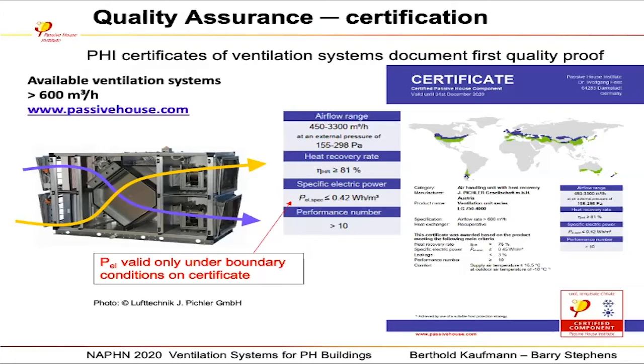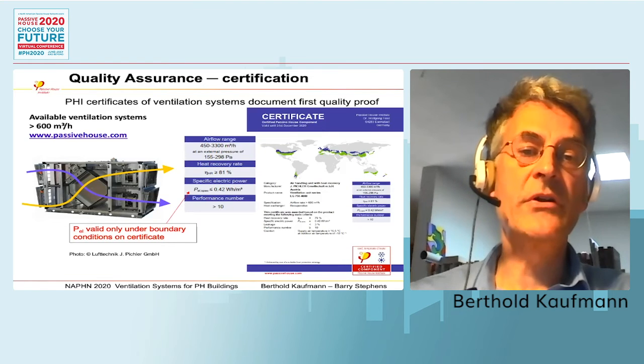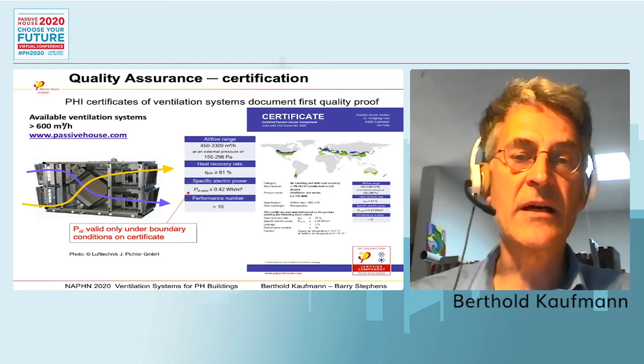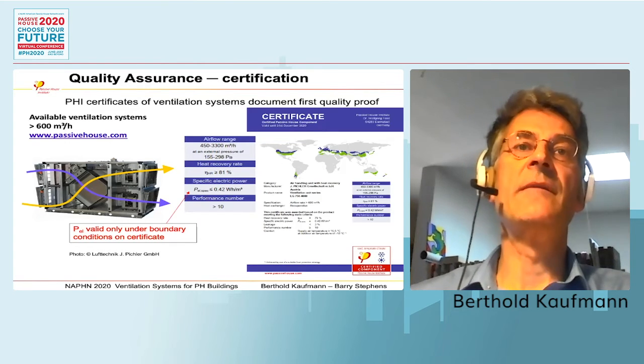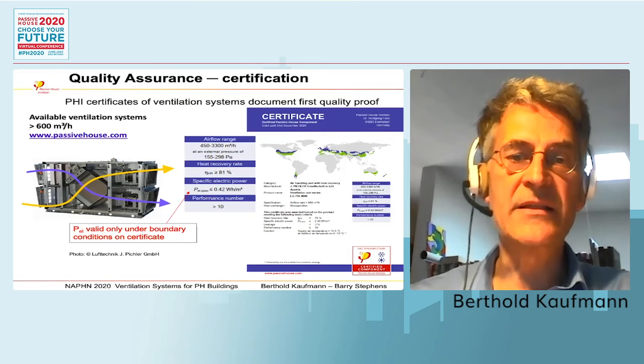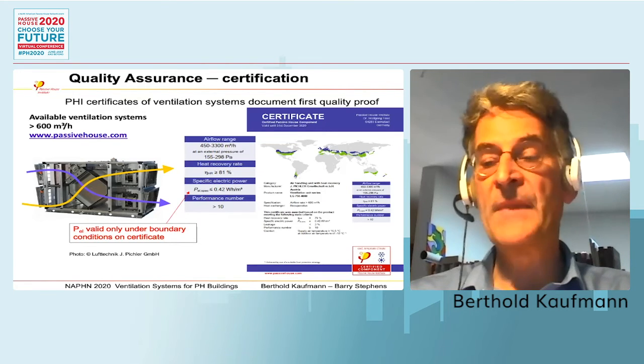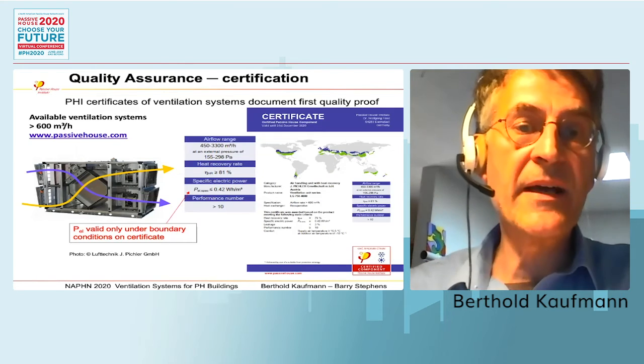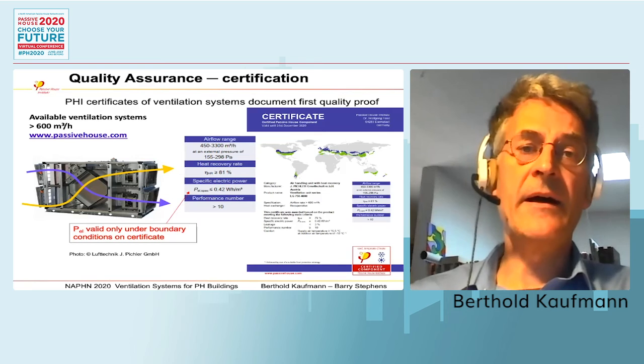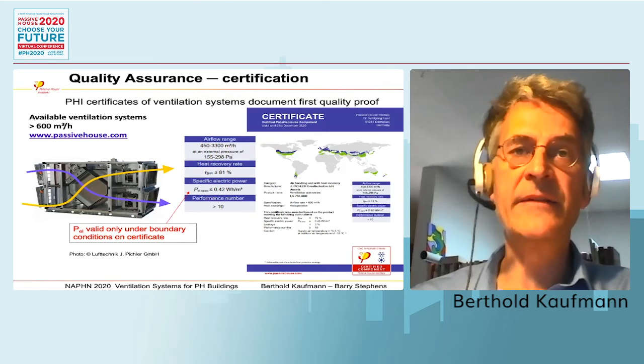In the second and third page of the certificate, there is a short description of the system, and last but not least, on every certificate you have the contact to the manufacturer, so you can go there directly. Well, the idea behind this certification process is we ask for third-party data about the ventilation system, not only manufacturer data, but reliable data, so that the systems can be compared. And you can go to our website, passivehouse.com. Many of the systems are available there with all the data.